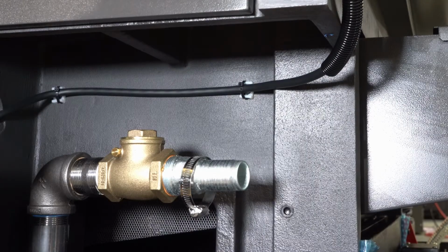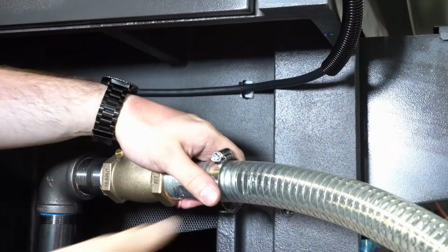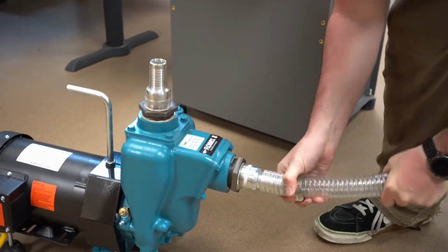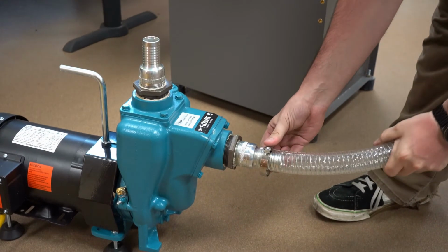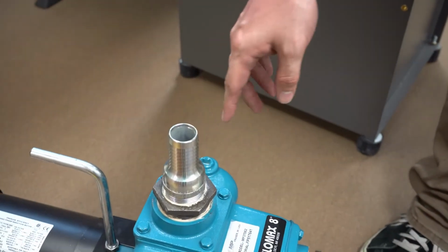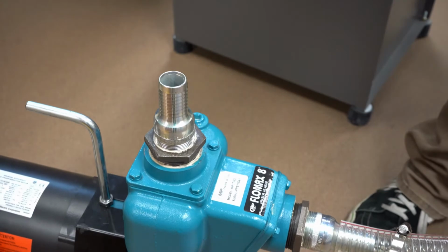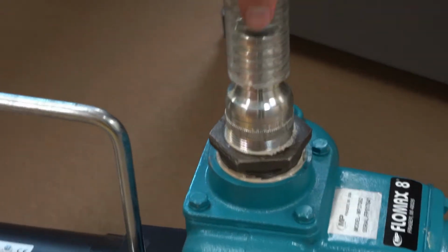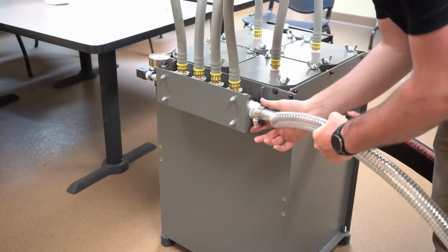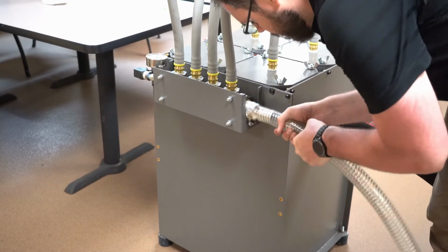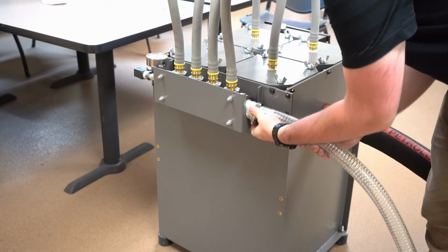Next, connect your hose and run it to where you'll be placing your pump. Connect the hose to the inlet of the pump on the front. Be sure to tighten the hose clamps. Then, prime the feed pump by pouring coolant into the top fitting until the casting is full. Then connect your outlet hose from the top of the pump. Then connect it to the inlet manifold on the purge. Then tighten the hose clamps.